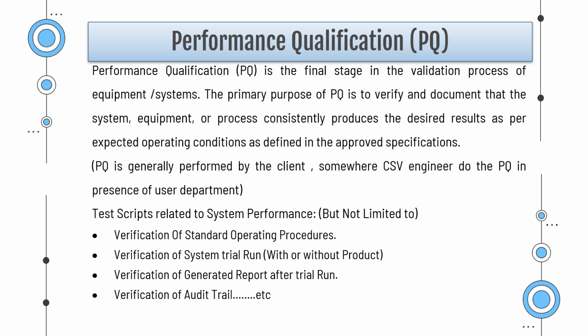Performance qualification, PQ, is the final stage in the validation process of equipment systems. The primary purpose of PQ is to verify and document that the system, equipment, or process consistently produces the desired results as per expected operating conditions as defined in the approved specifications. PQ is generally performed by the client. Somewhere CSV engineer do the PQ in presence of user department.